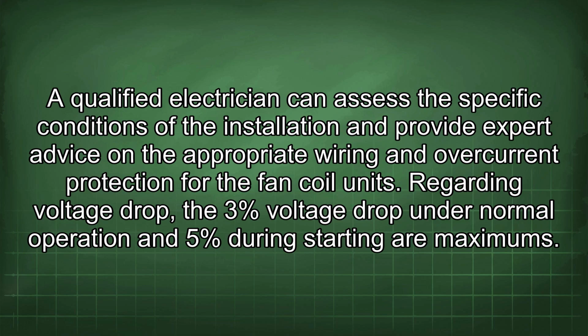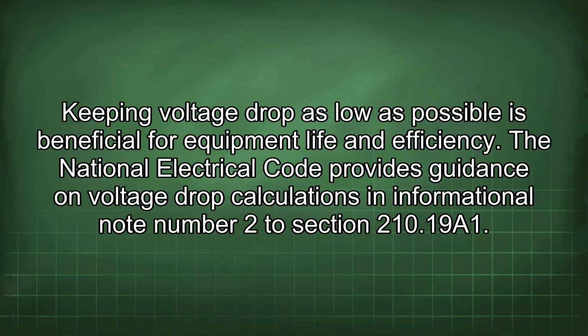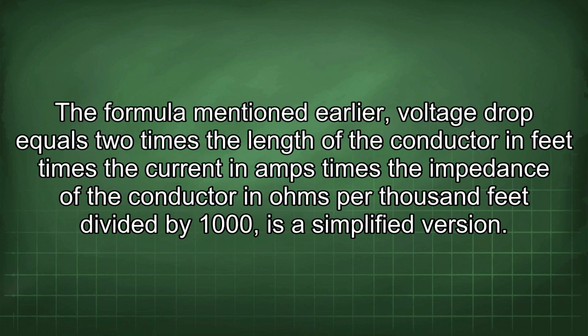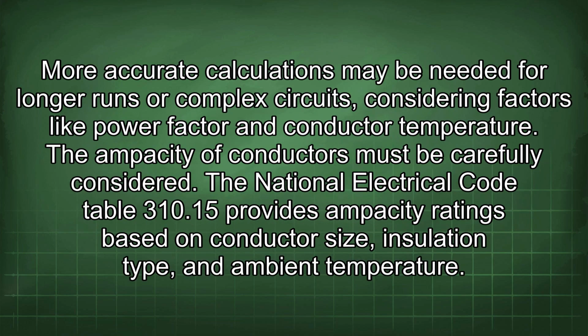Regarding voltage drop, the 3% voltage drop under normal operation and 5% during starting are maximums. Keeping voltage drop as low as possible is beneficial for equipment life and efficiency. The National Electrical Code provides guidance on voltage drop calculations in Informational Note Number 2 to Section 210.19(A)(1). The formula mentioned earlier, voltage drop equals 2 times the length of the conductor in feet times the current in amps times the impedance of the conductor in ohms per 1000 feet divided by 1000, is a simplified version. More accurate calculations may be needed for longer runs or complex circuits, considering factors like power factor and conductor temperature. The ampacity of conductors must be carefully considered.